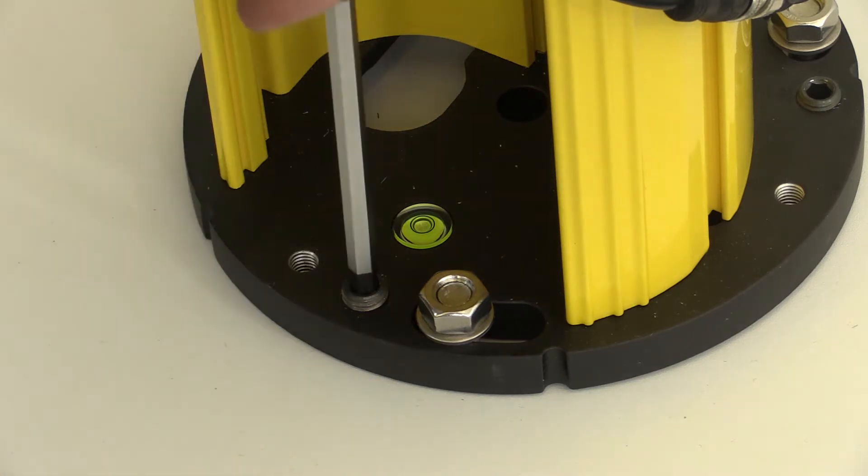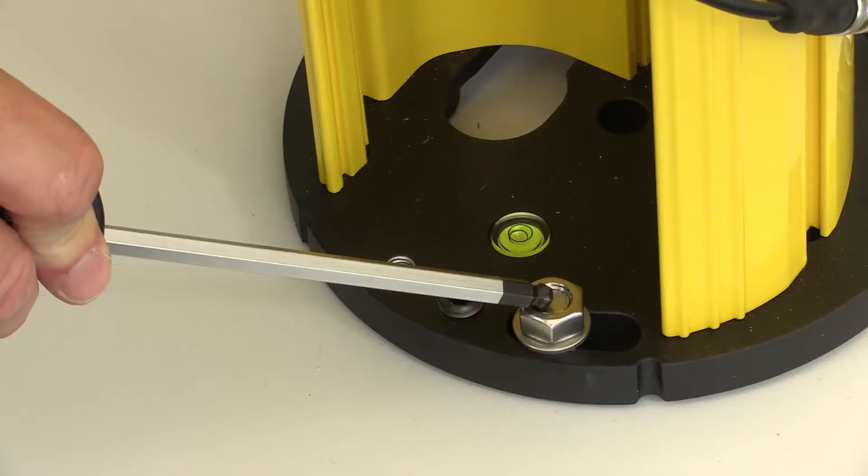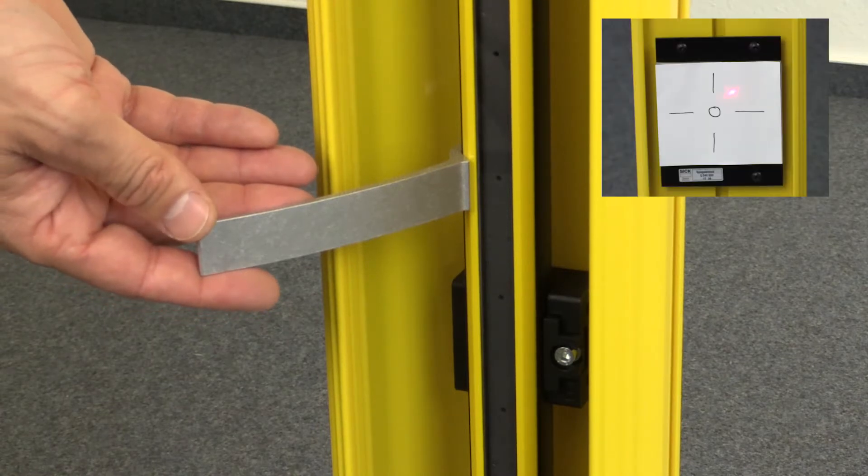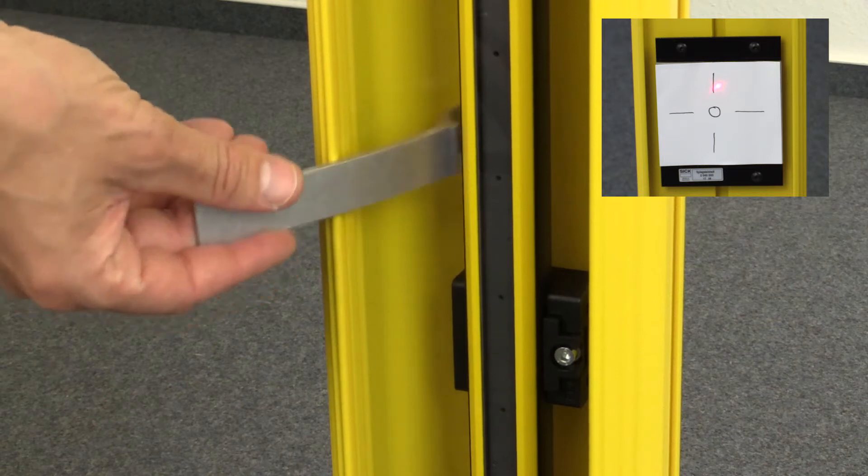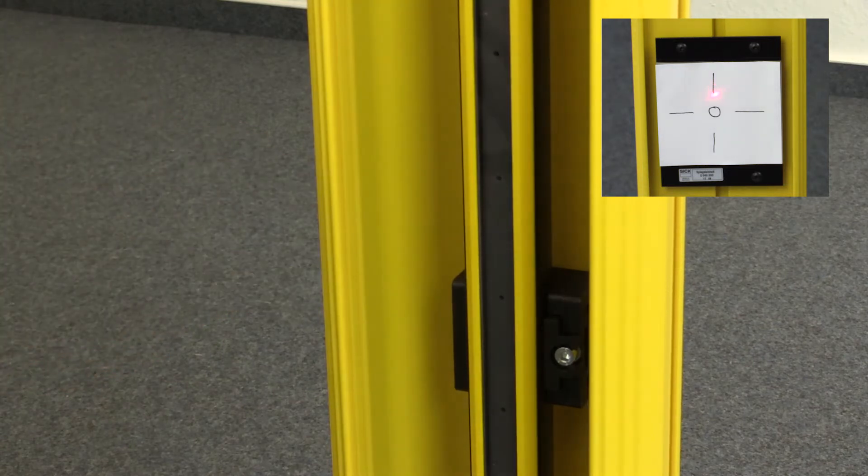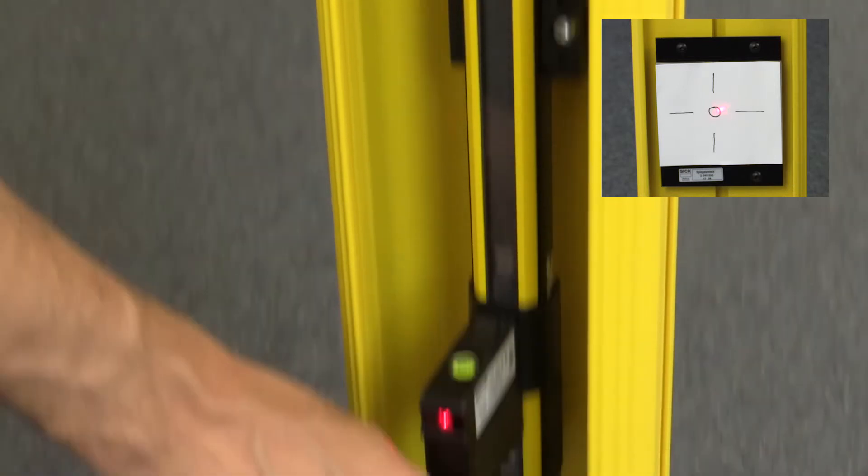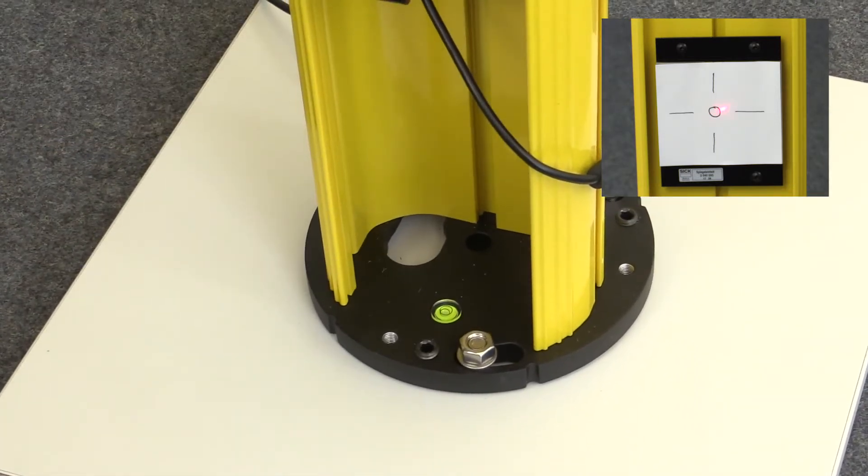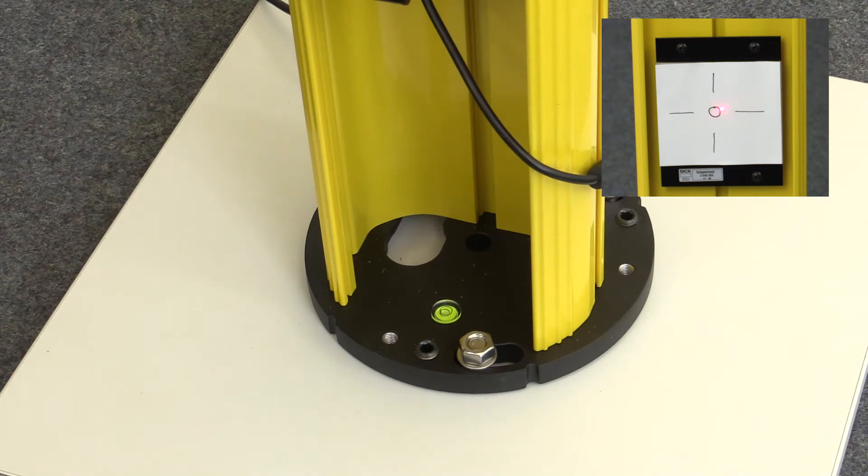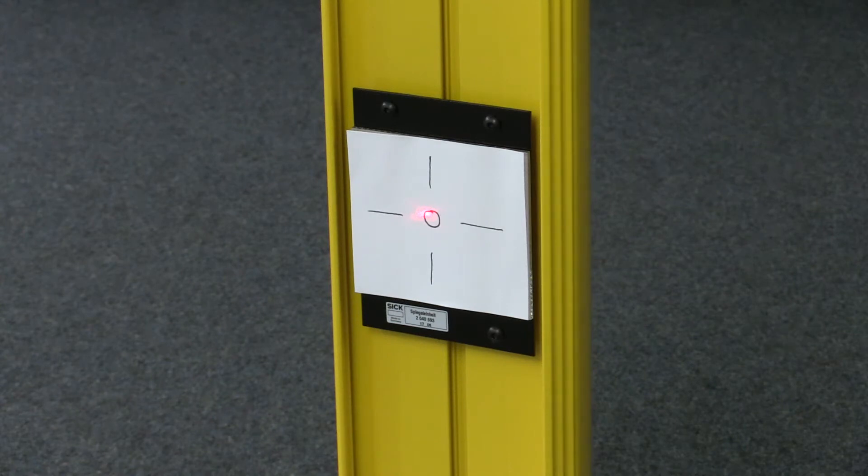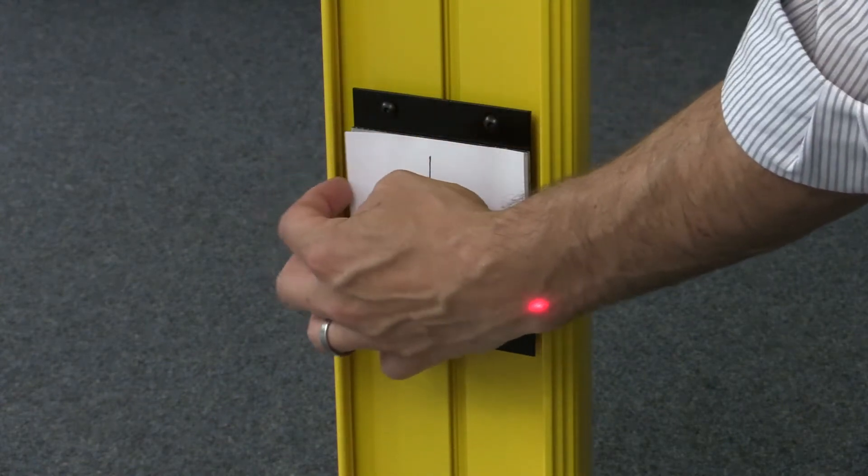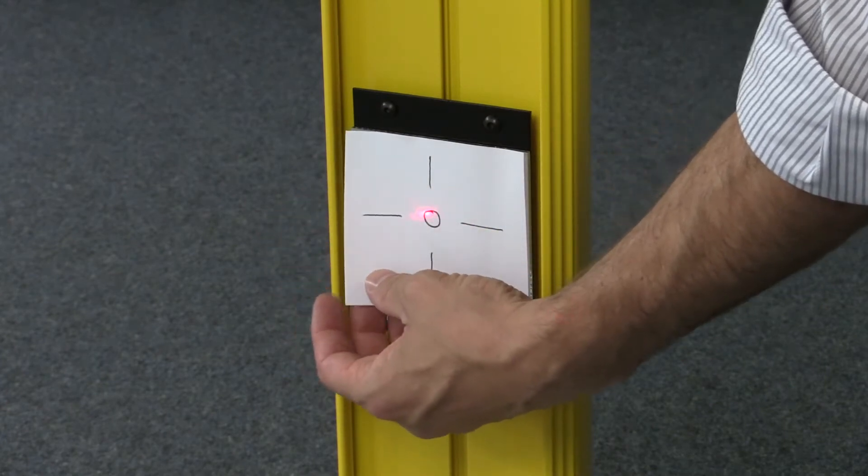Level the column and then fix the column on the floor. Turn the sender by using the alignment tool and make a fine adjustment for the horizontal positioning of the laser beam, until the laser beam hits the mirror of the mirror column. You have already seen that I have used a self-made target for helping to find the position of the laser beam.